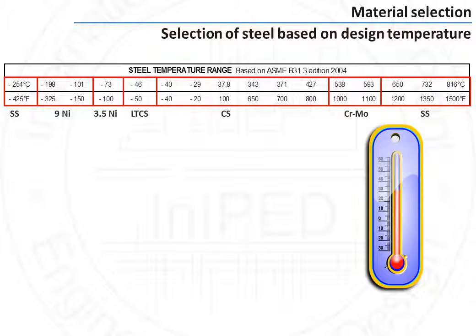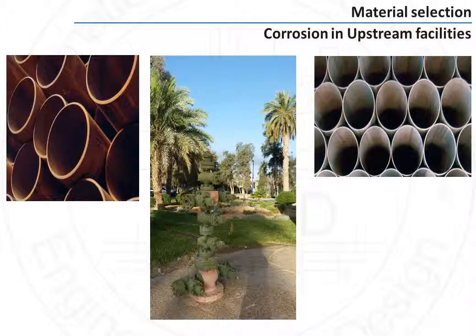The last parameter that influences material selection is the type of fluid and its corrosion aspects. Let's take an example which is the most common corrosion phenomenon found in upstream oil and gas facilities. The fluids handled contain gas mixed with oil and water. Water gets acidic because of the presence of acid gases such as CO2 and H2S in the gas, and acid water corrodes the steel.